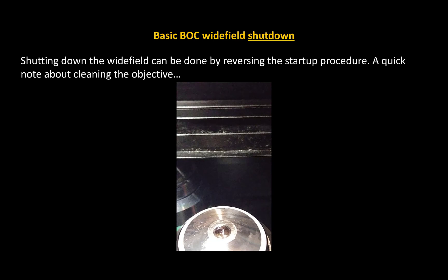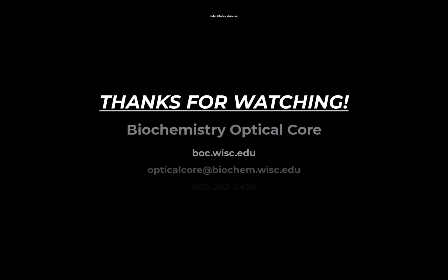The rest of it is simply turning off the power switches you turned on for your experiments — that means turning off the one labeled three, then labeled two, and then finally labeled one. That finishes up this video for the basic wide field setup. Stay tuned for more videos on how to operate the filters themselves, more about the cameras, and other topics pertaining to that part of the microscope. I'm also going to do a startup for the TIRF and the NSTORM components. As always, if you have any questions or comments, please send them to the BOC email. Thank you for watching.